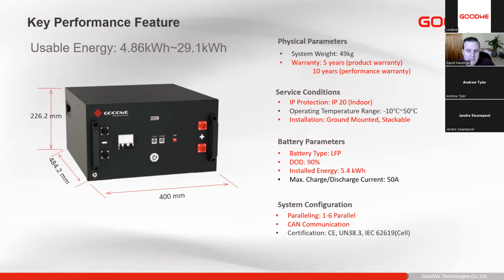All our batteries are LFP batteries. It does have a DoD of 90%, and it does have a 5.4 kilowatt hour capacity. So that's why the usable energy, as you'll see, is 4.86, because that's 90% of the battery capacity. And it has a max charge and discharge current of 50 amps. It is a 0.5C battery.